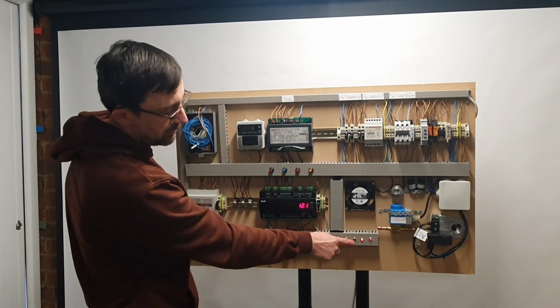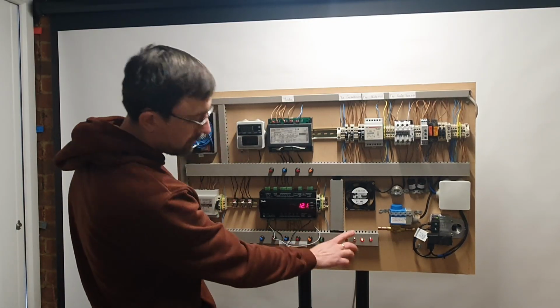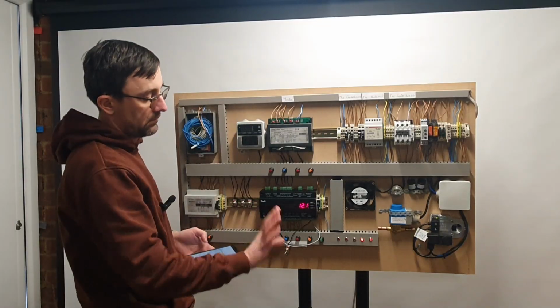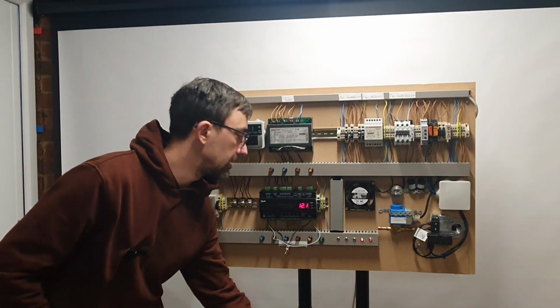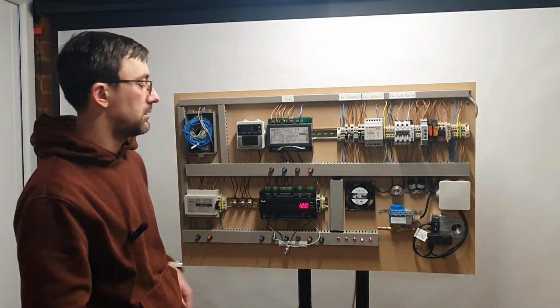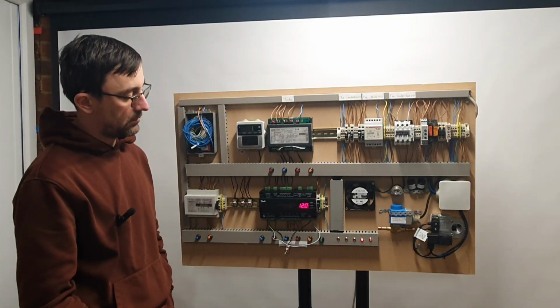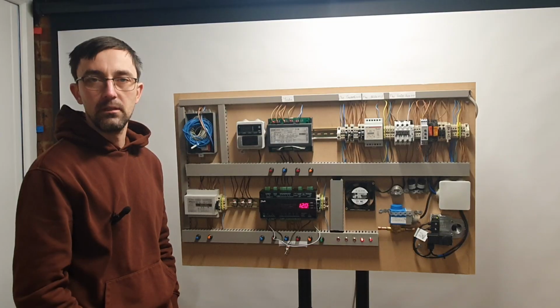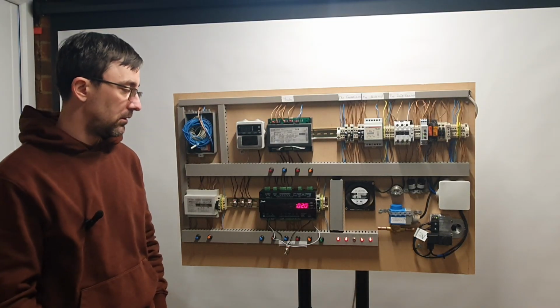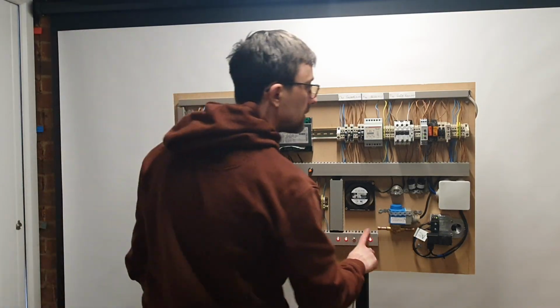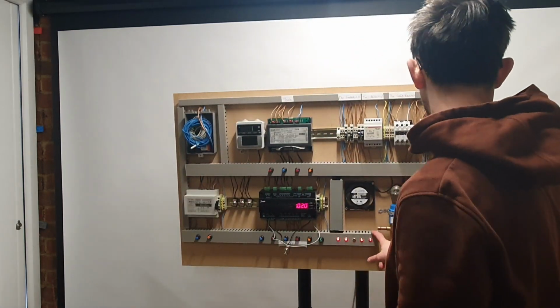12 degrees. Yeah. It switched off the defrost heaters because my defrost probe reads 12 degrees. So it's working. I don't know why I have a trip here. That is bugging me a lot.